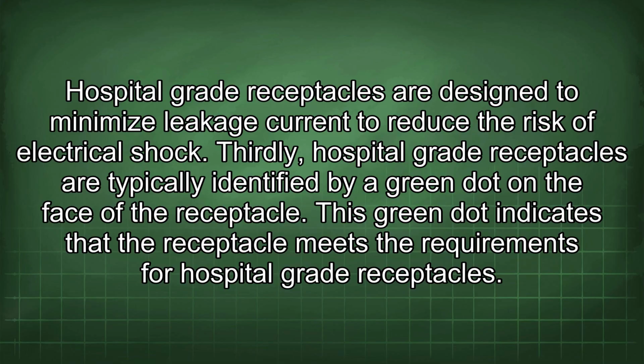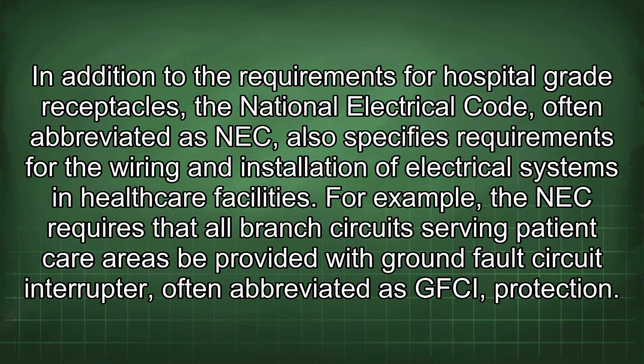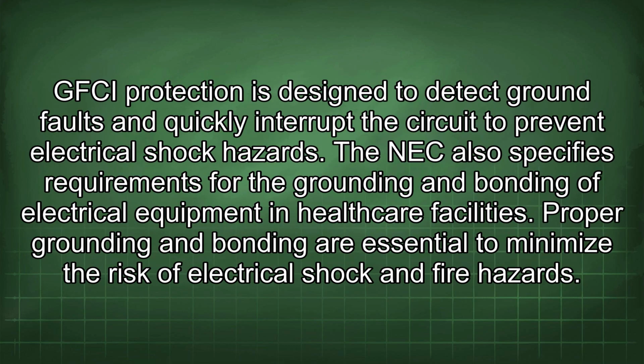Thirdly, hospital-grade receptacles are typically identified by a green dot on the face of the receptacle. This green dot indicates that the receptacle meets the requirements for hospital-grade receptacles. In addition to the requirements for hospital-grade receptacles, the National Electrical Code, often abbreviated as NEC, also specifies requirements for the wiring and installation of electrical systems in healthcare facilities. For example, the NEC requires that all branch circuits serving patient care areas be provided with ground fault circuit interrupter, often abbreviated as GFCI, protection. GFCI protection is designed to detect ground faults and quickly interrupt the circuit to prevent electrical shock hazards.